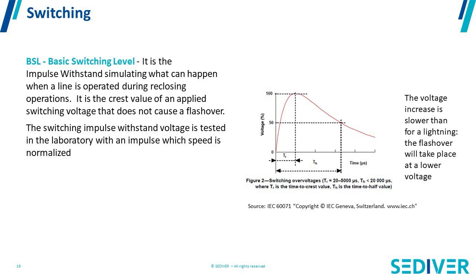Switching is a parameter that is not important at low voltage lines. For example, for a distribution line at 24 kV or a line at 110 kV, you don't need to worry about switching — the dominant parameter is lightning. Above 345 kV, lines are designed with switching impulse more than lightning impulse, because switching will occur at a lower value than the lightning impulse for a relatively long string — typically 345 kV and above.